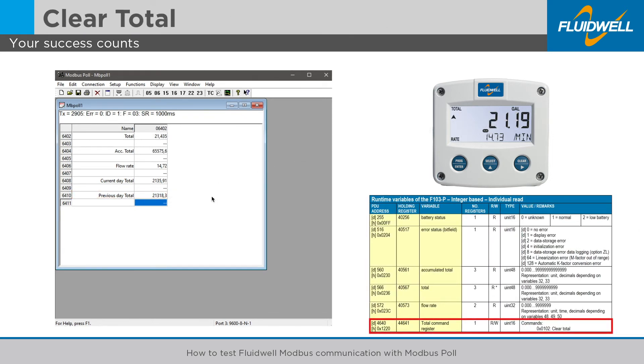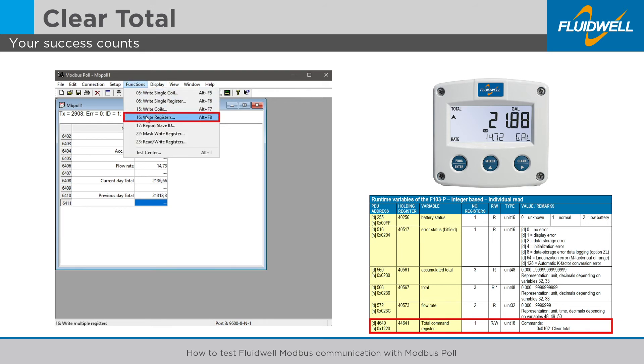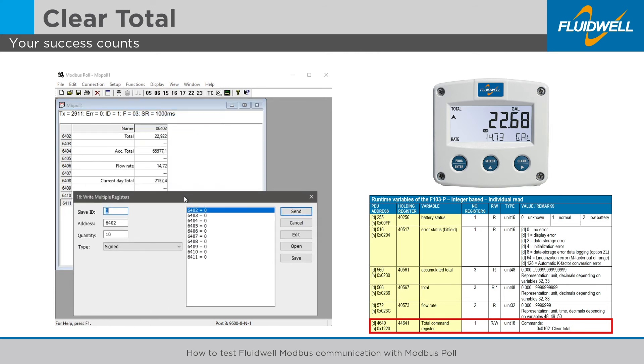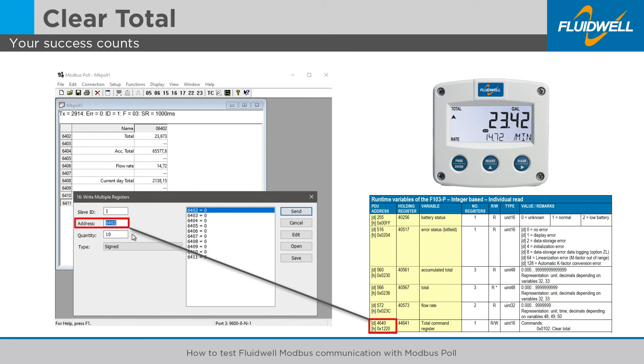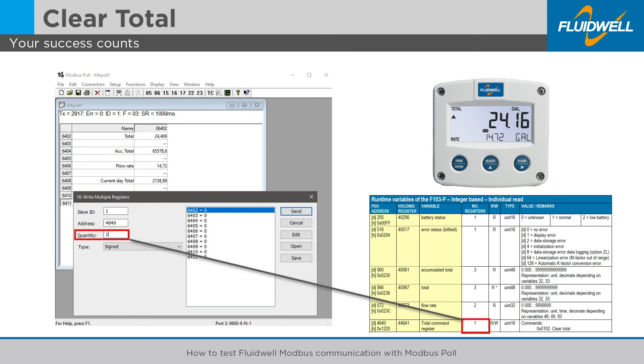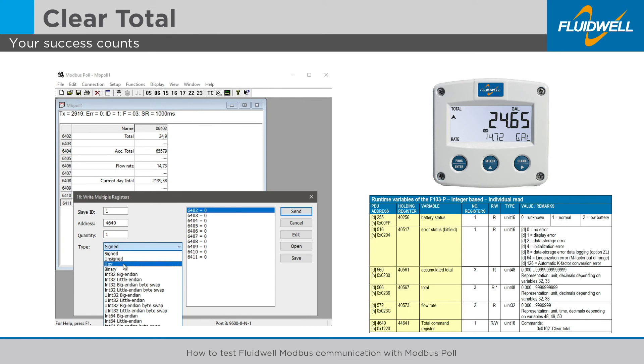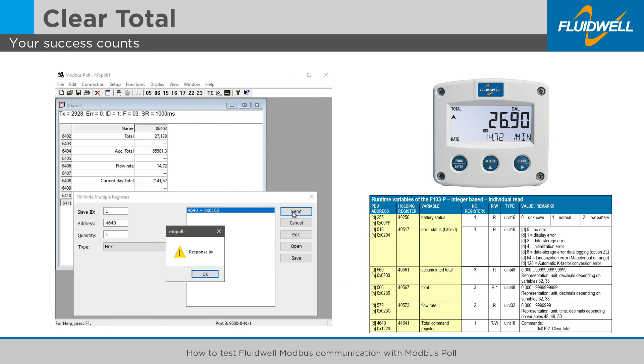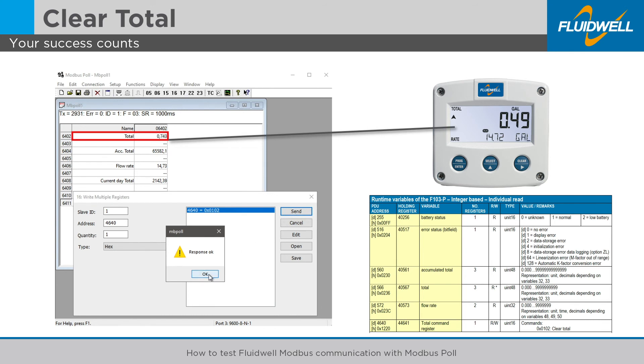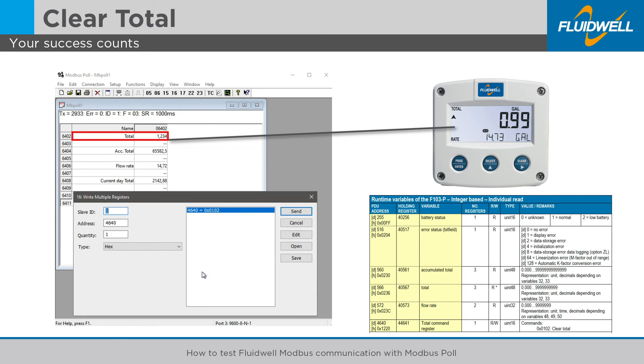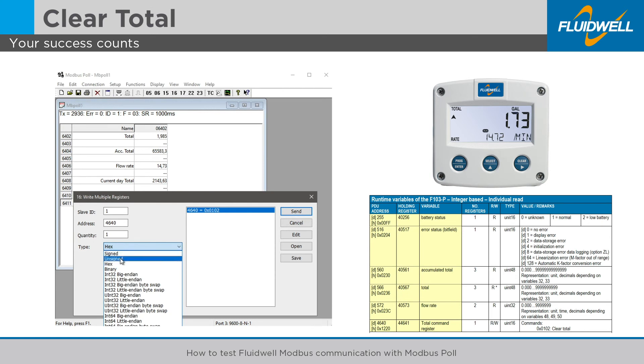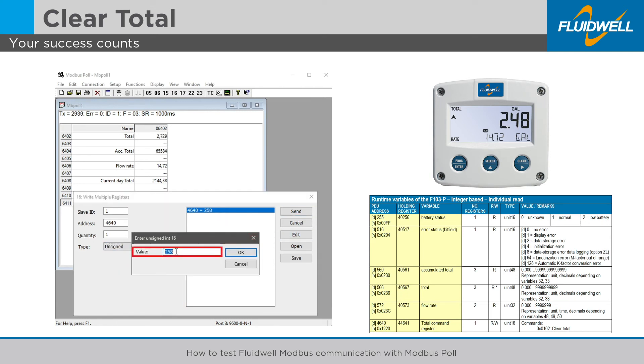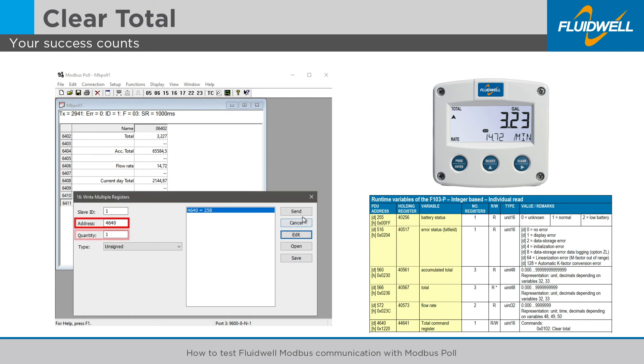To clear total by writing to the command register, use the following integer-based method with function 16, write multiple registers. Write to the total command register at PDU address 4640 in a single write action. Write a hexadecimal value of 0102, then write a decimal value of 258 to the total command register at PDU address 4640 in a single write action.